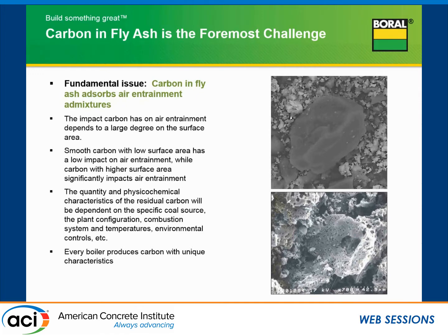Everything I'm speaking about today is based on personal experience. A lot of the data I'll show is from the company I work for. Every boiler we manage produces carbon of different characteristics. We have sites with identical boilers, identical megawatts, burning identical coal, constructed at approximately the same time — and these plants will still produce fly ash with carbon that has different characteristics. It's a function of the operation of the plant. They're mechanical systems; they wear, they're operated slightly differently. So the point is that every fly ash source will have different types of carbon in it.